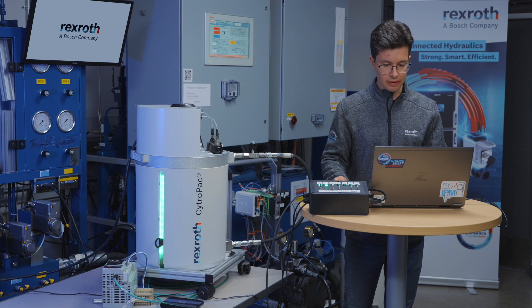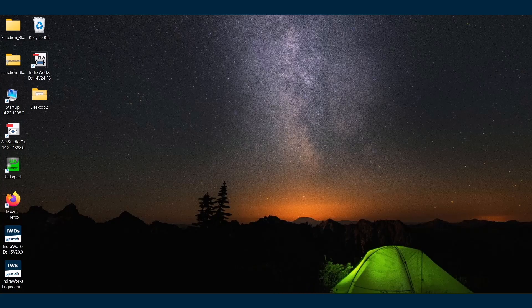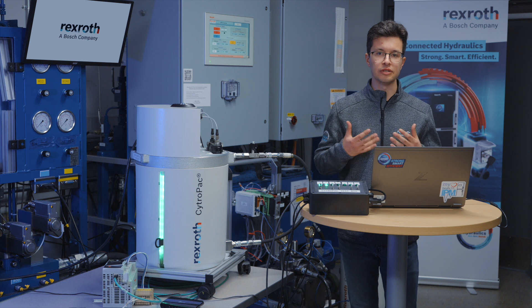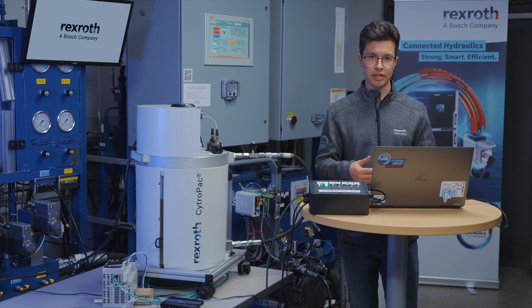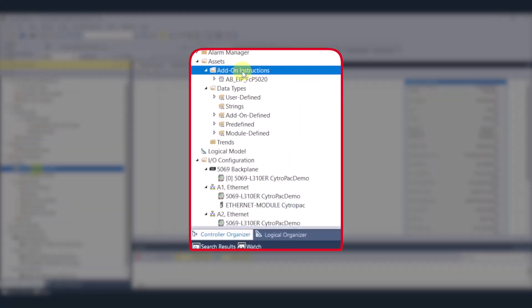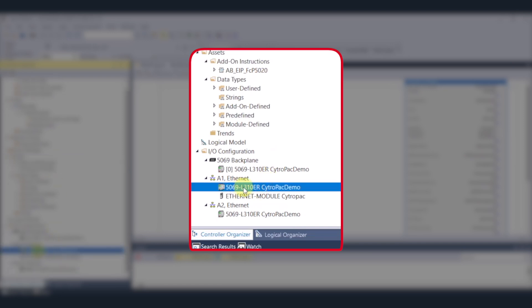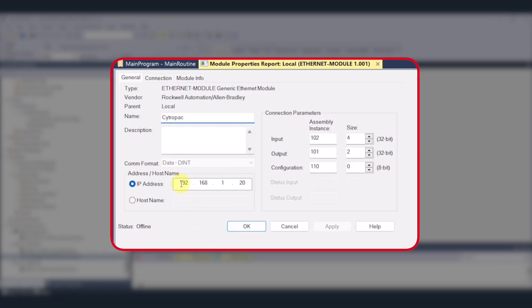Now that we have that set up, we're ready to communicate via the program. I'm going to open up ControlLogix Logix Designer. What I'm going to be using to do the communication is an AOI designed by Bosch Rexroth for the FCP 5020 — this is available to download on our website. To implement the AOI, you open up your program, import the add-on instructions: AB_EIP_FCP5020. Then under your PLC in your program, you're going to import an Ethernet module — you can call it whatever you want, in this case I called it Cytropac. You'll have your IP address set to the same one as set in IndraWorks DS, along with the connection parameters required to send data back and forth.